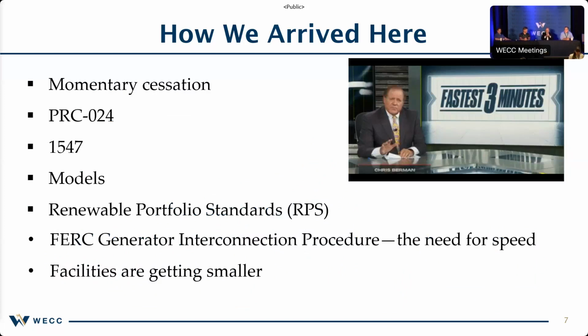So the very first thing we learned, which to a utility person is very unique, right? We're talking with all of these solar facility and inverter OEM people, and we asked them, why did you trip during that disturbance? And they looked at us and said, well, we didn't trip. We just quit injecting current. We blocked. And for an old utility guy, I hear that and I'm like, how is that not a trip, right? And so that term momentary cessation, that was when we first learned of that.